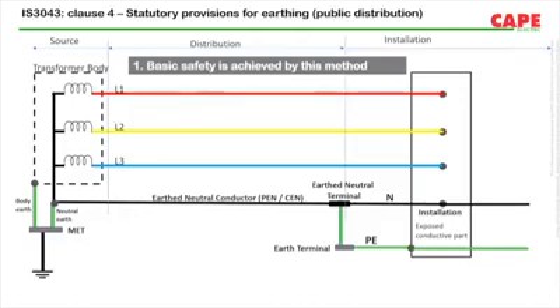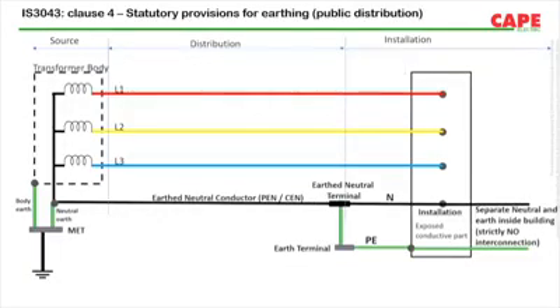Exposed conductive part in an installation is connected to the earth terminal of that installation. This earth terminal is linked to the earthed neutral terminal of the installation. This means the fourth wire running between the transformer and the installation is not a neutral conductor but a combination of neutral and protective earth, which can be called a PEN conductor, or combined earth and neutral. IS 3043 explains this as combined earth and neutral conductor, or CEN.